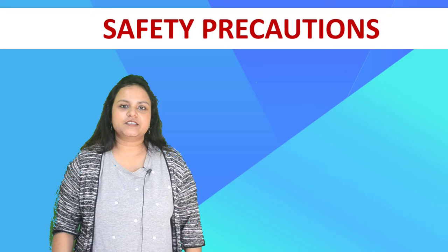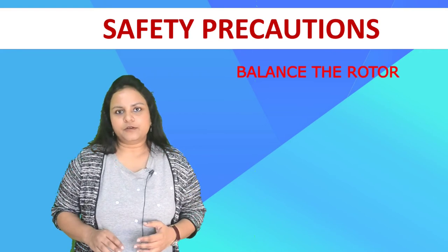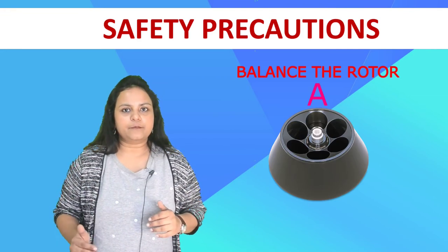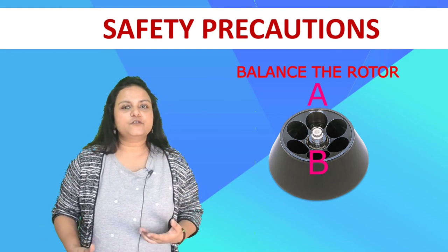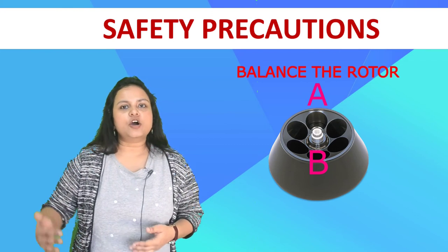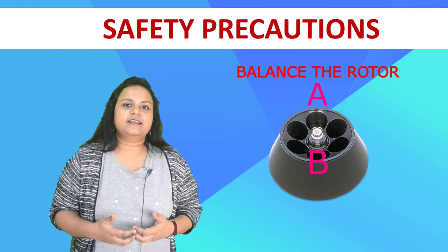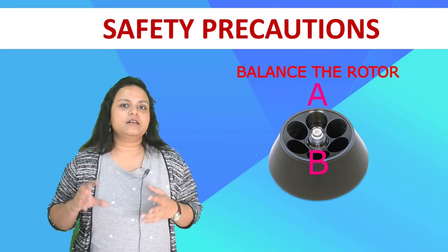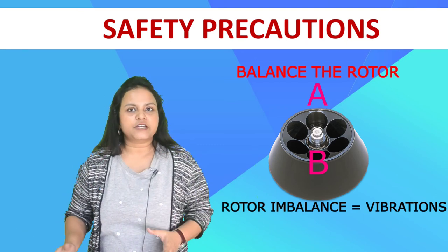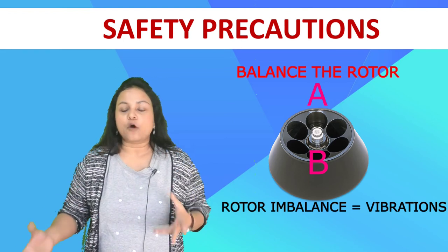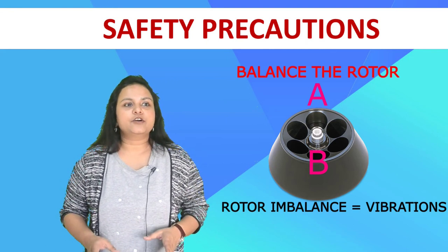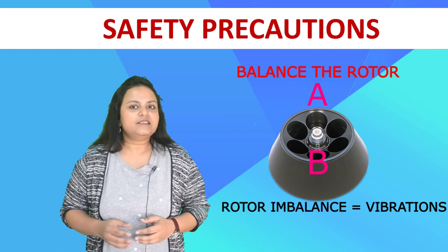Now let's talk about safety features in a centrifuge. While using a centrifuge, you must balance the rotor properly. Since the rotor is circular and symmetrical, if you place a sample at one position, you must have an equally weighing sample directly opposite it. If you don't have another sample, you must use a counterbalance or dummy tube filled with water placed completely opposite your sample. Failure to do so leads to rotor imbalance — an imbalanced rotor will vibrate a lot, transferring vibrations to the centrifuge framework, causing it to wobble. In fact, centrifuges with fiber bodies have been known to crack because of such imbalances.